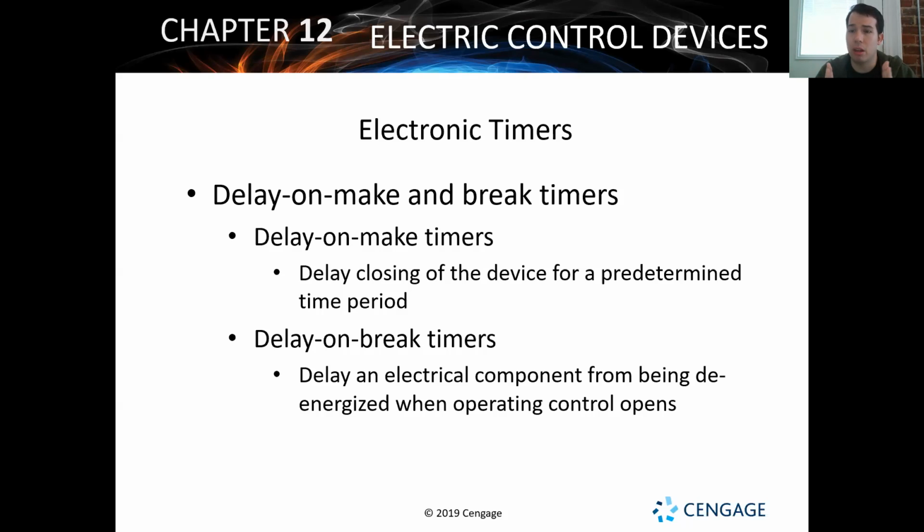That will make it so that basically everything goes back to that board still. And on that board, a lot of times you'll have a set of dip switches, or dual inline package switches. Those can be turned on in different directions to control whether it's going in heating mode or cooling mode and how long of a delay. That's the other thing. So for heating, you can have it where that fan stays on for a longer period of time versus the cooling mode. You want the fan to cut off maybe 30 seconds after it's done going through the cooling cycle.